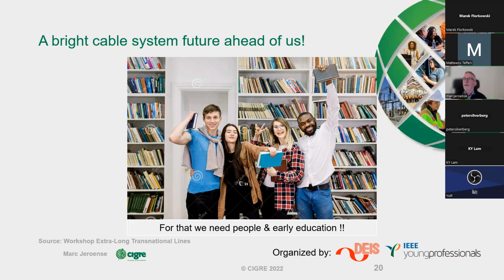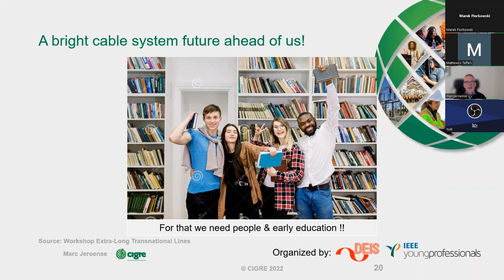Thank you. Well, the typical lifetime that is contracted, which is maybe not the same as what we know, is 40 years for interconnectors. Cables connected to wind farms have an economical lifetime of, say, 20 to 25 years, somewhat shorter. But for typical interconnectors, we say it has to survive at least 40 years. If you look back, we do not see typical signs of aging such that DC cables tend to stop living after 40 years.